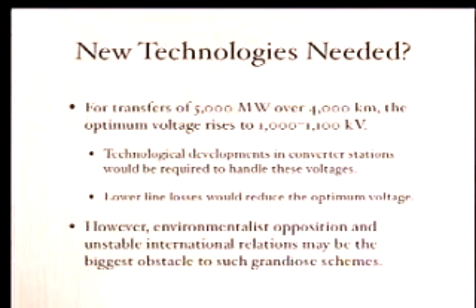For transfers of 5,000 megawatts or more over 4,000 kilometers, the optimum voltage for your DC link rises to 1,000 to 1,100 kilovolts. Technological developments in converter stations will be required to handle these. This is where some technological development is needed.